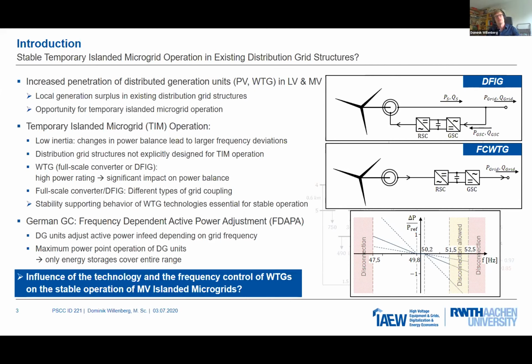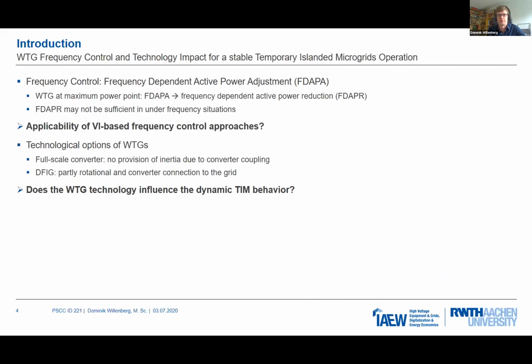So not only this frequency control approach, but also the technology, since it's partly, in case of DFIG, partly rotationally coupled to the grid and partly inverter coupled, has an influence on the stable operation, and it's necessary to determine how large this influence is.